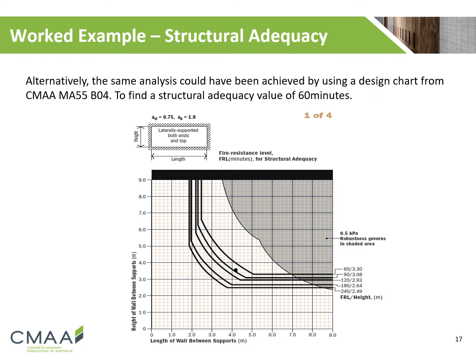Alternatively, the same analysis could have been achieved by using a design chart from CMAA Manual 55 Section B04. For a wall that is 4.2m long and 3.5m high, we can easily see that the structural adequacy value can be determined to be 60 minutes from the design chart.